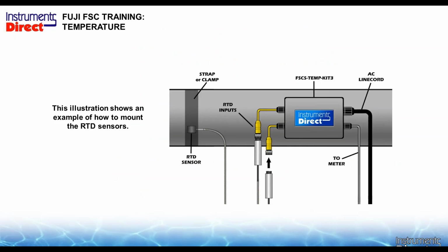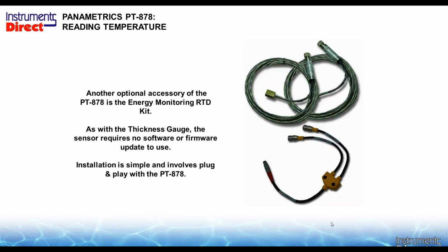Here's an illustration of the Fuji temp kit, and it basically is a close shot here. We take an RTD, we use a thermal compound, looks like a zinc oxide, apply that to the pipe, and we strap it on with a flex tape and leave it there. You can re-insulate after it, not going anyplace. So a precision RTD, considerably more accurate than the stated accuracies there, and calibrated to work with the system. It's plug and play. The GE PT878 also has similar RTDs. They're strapped on the outside of the pipe, and they come through their IO port right here through a Y connector.